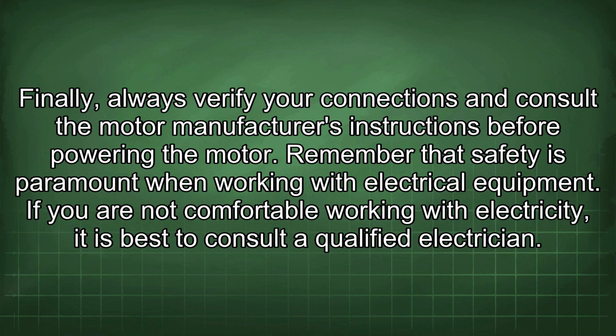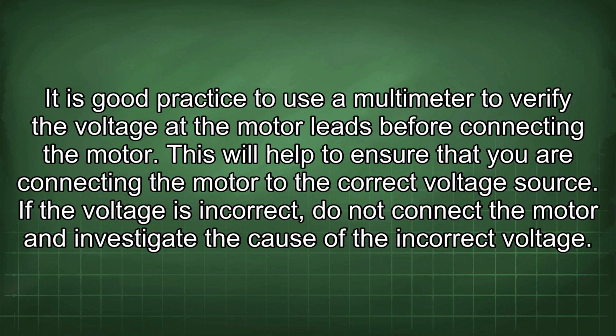Remember that safety is paramount when working with electrical equipment. If you are not comfortable working with electricity, it is best to consult a qualified electrician. It is good practice to use a multimeter to verify the voltage at the motor leads before connecting the motor. This will help to ensure that you are connecting the motor to the correct voltage source. If the voltage is incorrect, do not connect the motor and investigate the cause of the incorrect voltage.